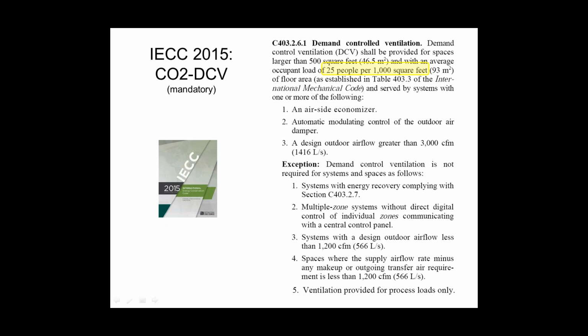All the economizer controllers have an input waiting for this sensor. All you really have to do is buy the CO2 sensor, mount it on the wall, wire it to the rooftop or the economizer controller on your split system or whatever you have. There are some exceptions when you don't have to do it, like really small systems, less than 1,200 CFM of outside air, or systems that have ERVs, because if you have an ERV, you're already kind of taking care of that outside air energy savings in another way. So there's a few exceptions, but in general, plan on spaces with high density occupancy, such as classrooms, movie theaters, sports arenas. Plan on those spaces probably having to have CO2 sensors.